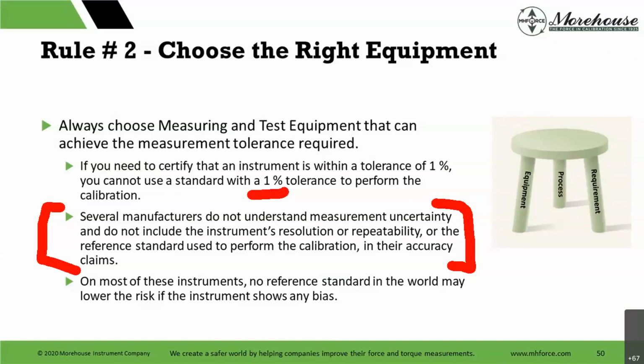You don't know. You ask them. I sat down with a good colleague when I was presenting at a NIST function, and they told me they asked for an accuracy specification. Can I have the data? And the manufacturer gave them data that was outside of the tolerance, both high and low, and told them they were using the average. Not going to mention the manufacturer there, but that is what happens. You don't know. So if you don't know, you can ask.